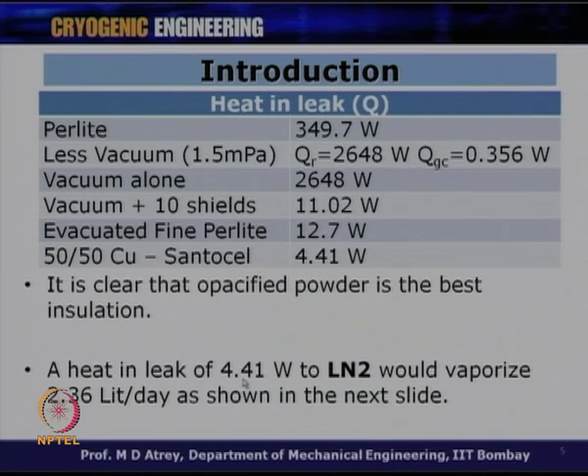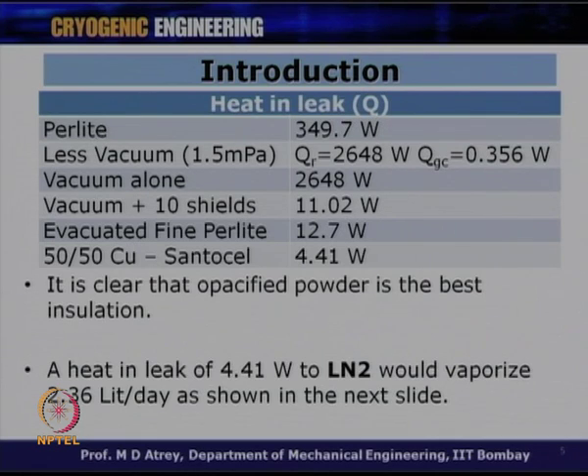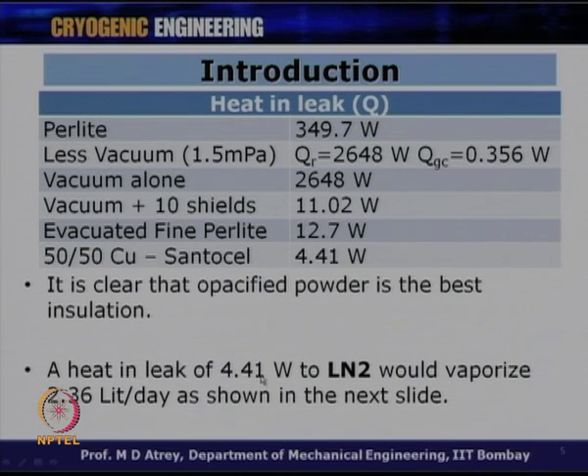A heat in leak of 4.41 W to liquid nitrogen would vaporize around 2.36 liters per day. Let us see how we calculate this rate of evaporation, as it is a useful tool for further calculations. The latent heat of liquid nitrogen is around 200 kJ/kg and density is 807 kg/m³. One meter cube equals 1000 liters and one day has 24 hours.